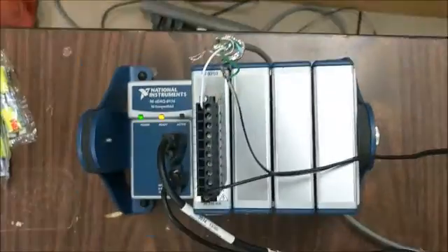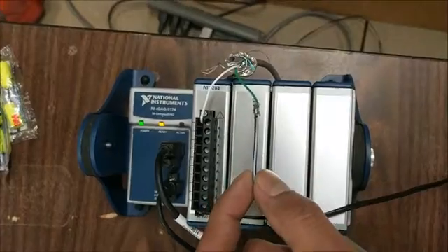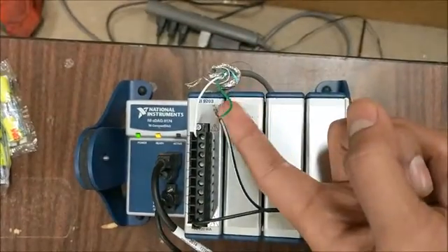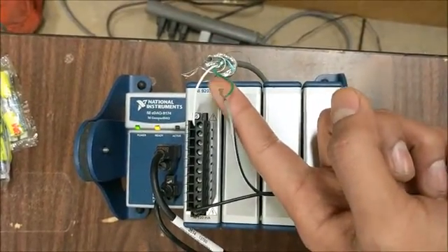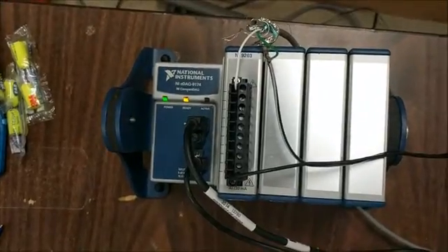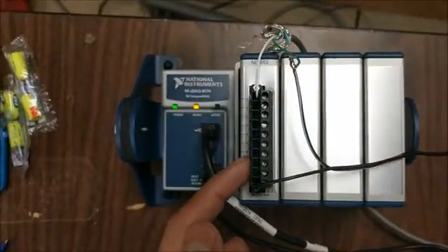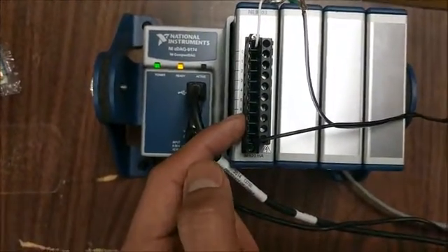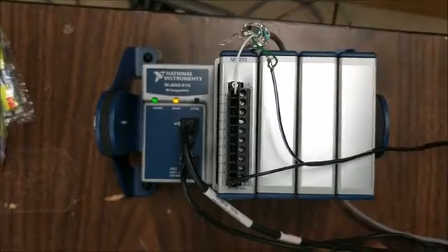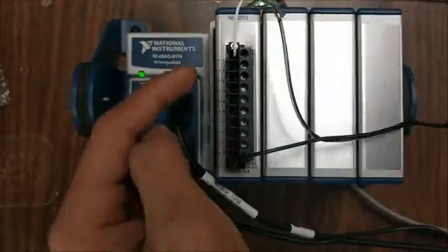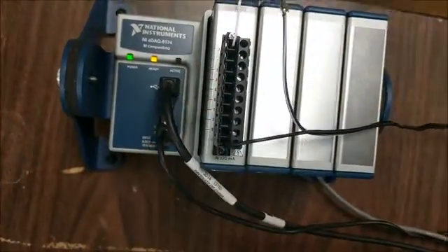That's the power source. The positive of the power supply goes to the positive of the transducer positive wire, and the common or negative or ground goes to COM port over here. You can use any one of those 8 channels to get current feed in from the differential pressure transducer. I'm using port 0 over here, but you can use any one of those.